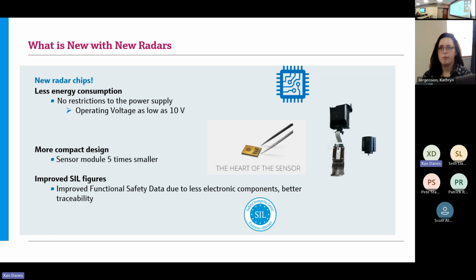Now, if I look at what the newer radars bring to the table, my sensor module is much smaller. The measurement fundamentally takes place now on a chip - not a semiconductor chip, but a chip on the order of a half inch by half inch. For those involved in functional safety, anytime we reduce electronic components, there are fewer possible things that can fail, in particular things that can fail in a dangerous or undetected way. Our functional safety data gets much better the simpler the measurement gets.